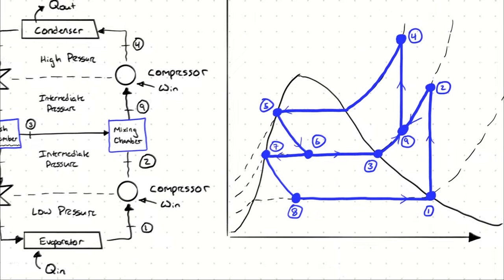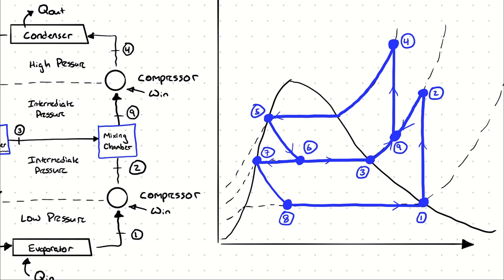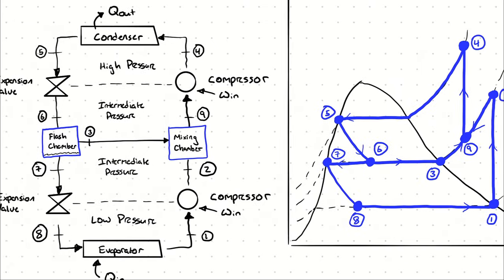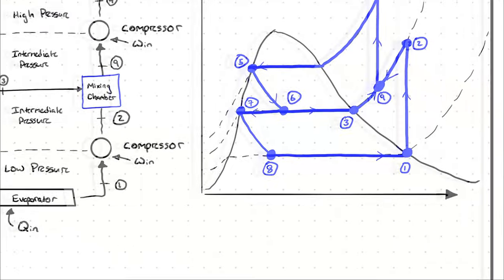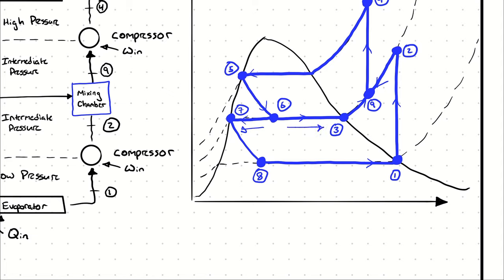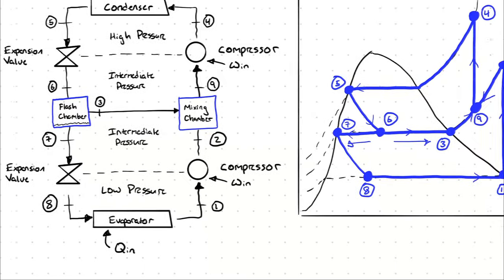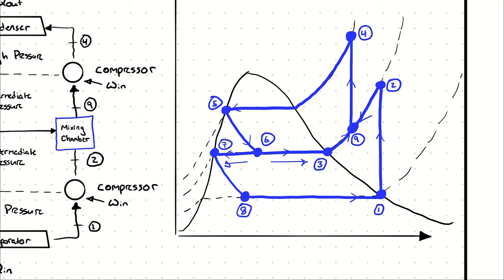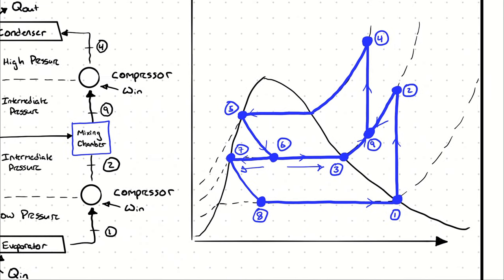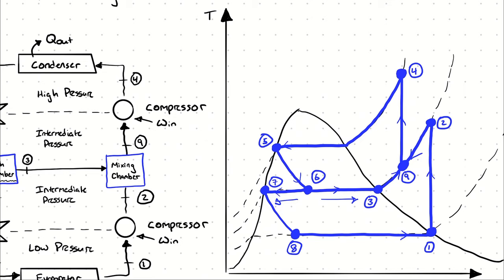Looking at the TS diagram, we can get a better idea of what's happening. We have a stream at 4 and 5, representing how much heat is being pushed out of our condenser. It's expanded across an expansion valve at state 6. Some of it leaves as liquid at 7, some as vapor at 3. The stream at 7 is expanded again down to low pressure at state point 8, pushed across an evaporator to state point 1. The process from 1 to 2 is an isentropic compression process drawn as a vertical line up to the intermediate pressure. State points 2 and 3 are mixed together to produce state 9, whose relative position between 3 and 2 is represented by the proportion of mass flow rates. Then state point 9 goes through an isentropic compression process to the high pressure at state point 4.